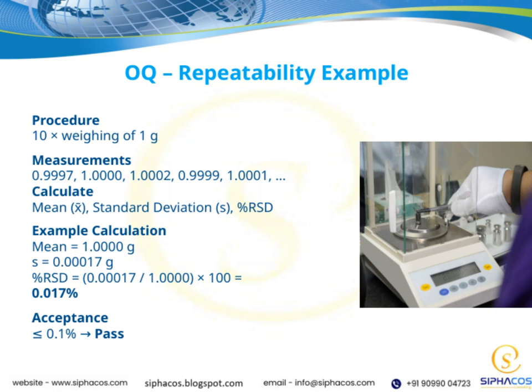The measurements we obtained are 0.9997, 1, 1.0002, 0.9999, 1.0001, and so on. Next, we calculate the mean, or average, of these measurements. In this example, the mean comes out to 1 gram. We also calculate the standard deviation, which measures how much the individual measurements vary from that mean. Here, the standard deviation is 0.00017 grams. Then, we determine the percentage relative standard deviation, or percent RSD.